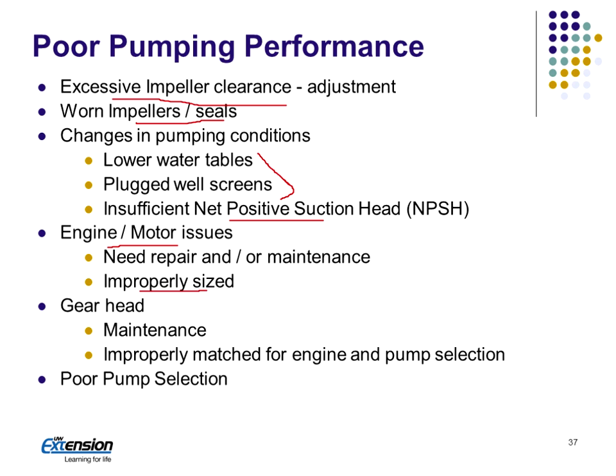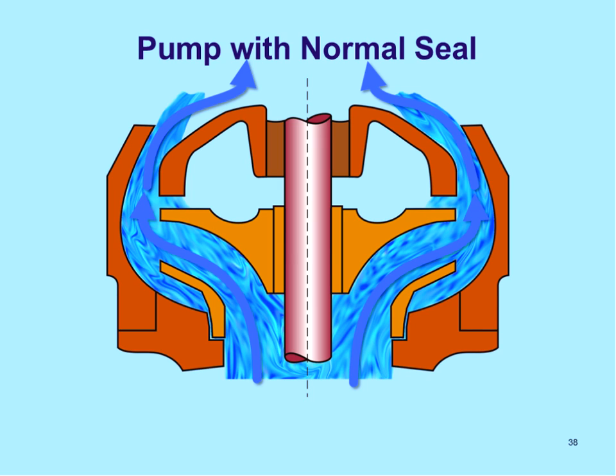So it could be that we need to replace the motor. Gear head maintenance: changing oil, making sure the gears are properly lubricated and matched correctly for the engine and the pump to work together properly. And then sometimes the pump is just the wrong pump for how it's being operated today, if we get out of that sweet spot for the efficiency.